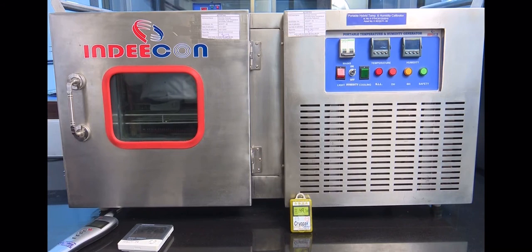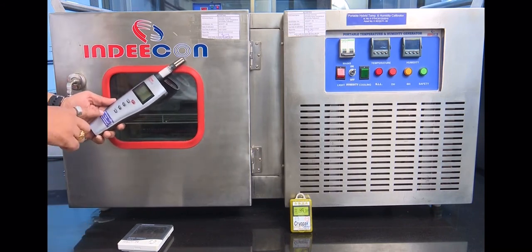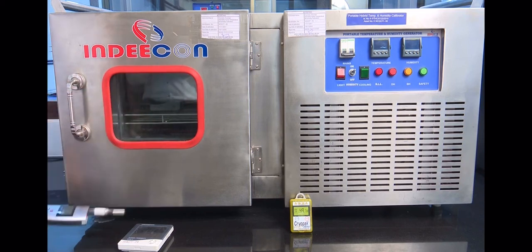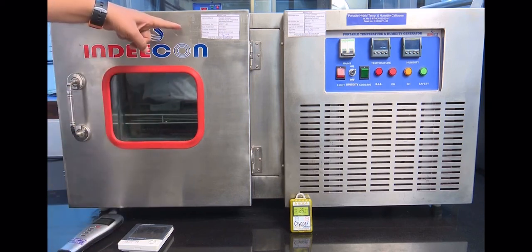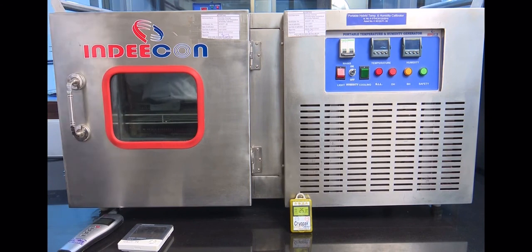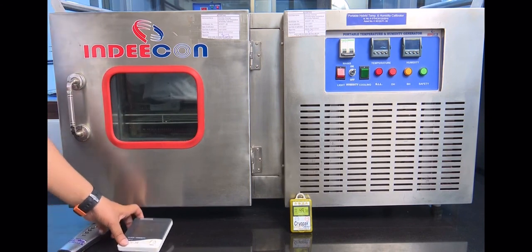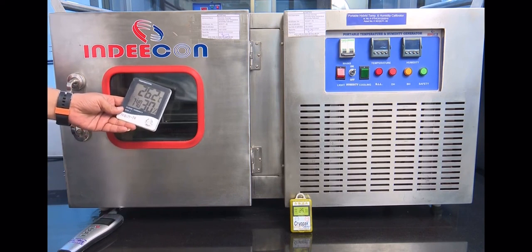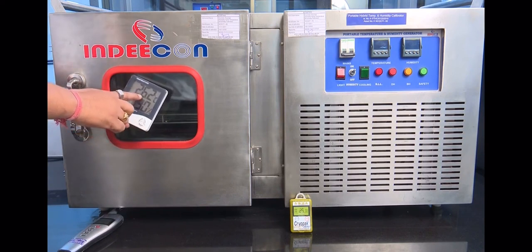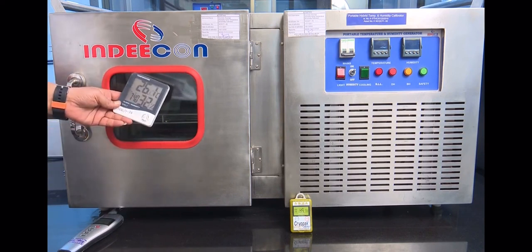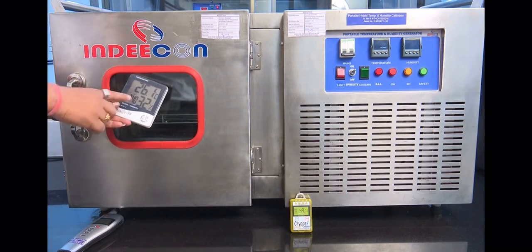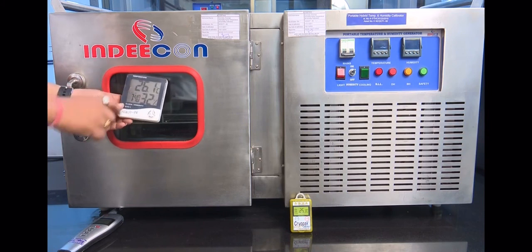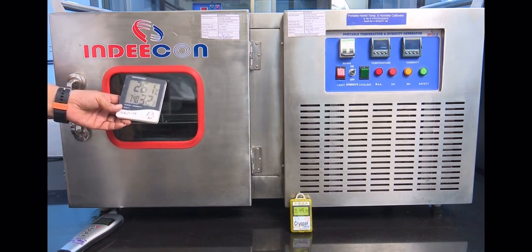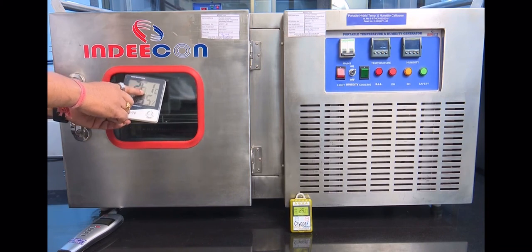For calibration, I am using two reference instruments, thermohygrometer and environment chamber. This is a digital thermohygrometer having two parameters, humidity and temperature. Humidity range is 10 to 95% RH and 1% RH least count. Temperature range is 0 to 50 degrees centigrade and 0.1 degrees centigrade least count.